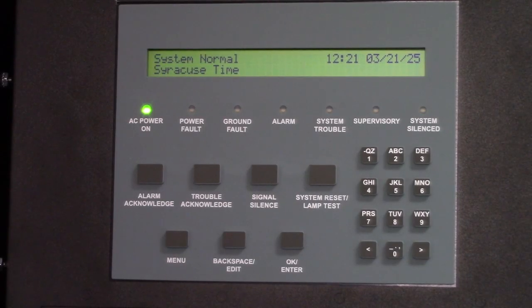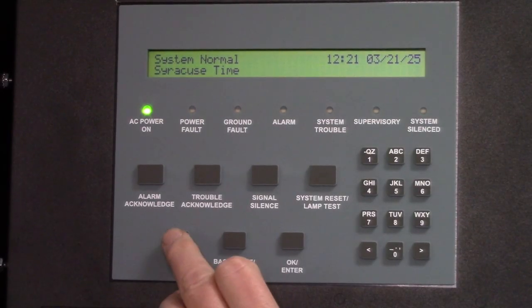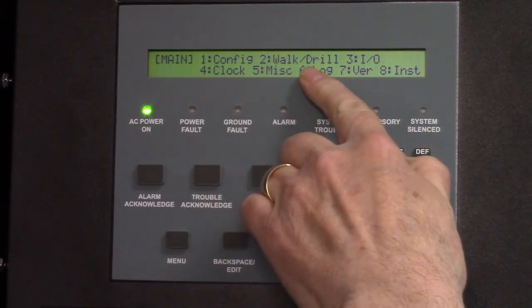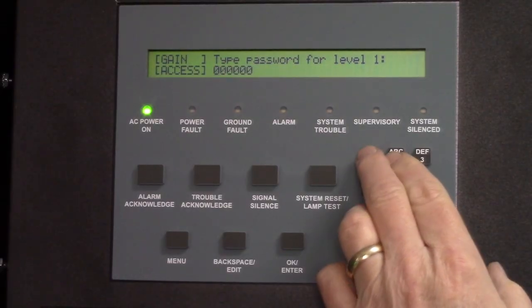To place a Gamewell-FCI E3 system in walk test mode, it's a pretty simple process. Start by pressing the menu. Walk test is selection two. The password for level one is typically all ones.